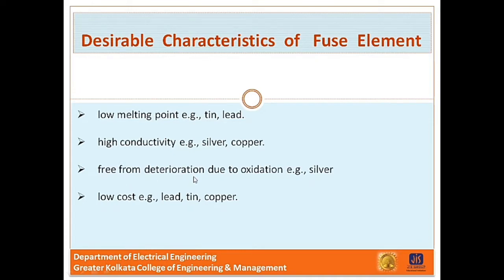It should be free from deterioration due to oxidation — for example, silver. And it should be of low cost — for example, lead, tin, and copper. No material possesses all these characteristics. For instance, lead has a low melting point but high specific resistance and is liable to oxidation. Similarly, copper has high conductivity and low cost but oxidizes rapidly. Therefore, a compromise is made in the selection of material for a fuse.